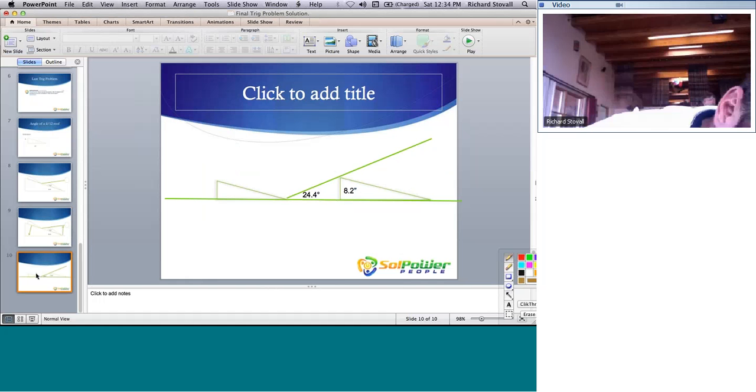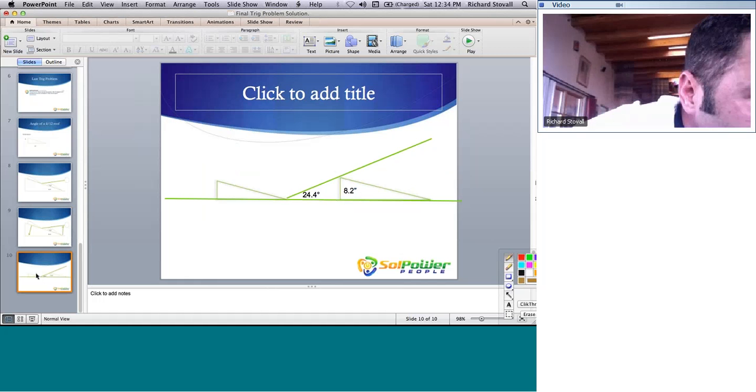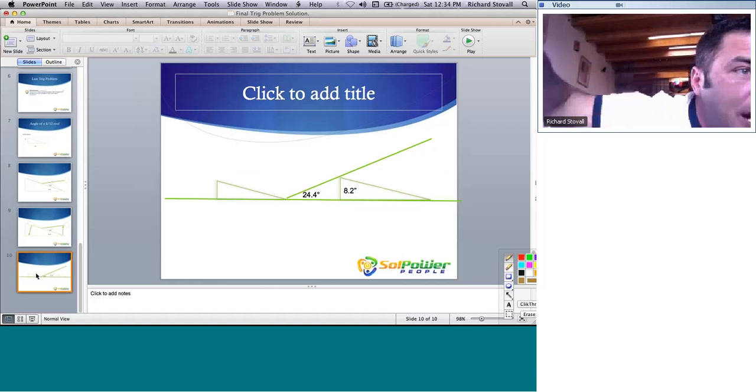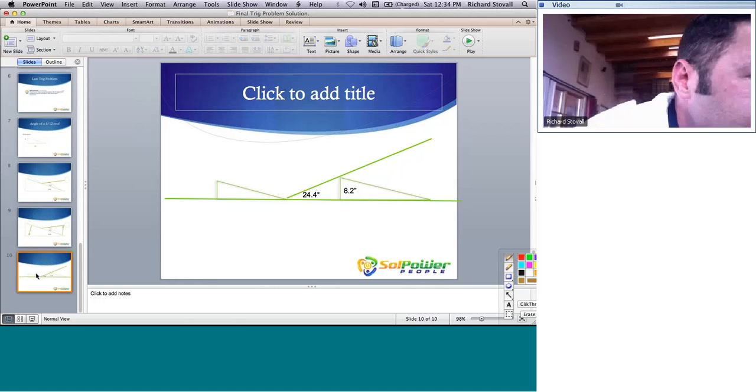What we made note of is basically that you take the solar altitude and add it to the pitch of the roof if you're talking about a roof mount on a pitched roof. That's correct, because from the roof's perspective, the sun is higher in the sky. The altitude angle of the sun from the roof's perspective is just however many degrees up the roof's pitch is. So it makes for a shorter shadow and gives you an accurate measure.